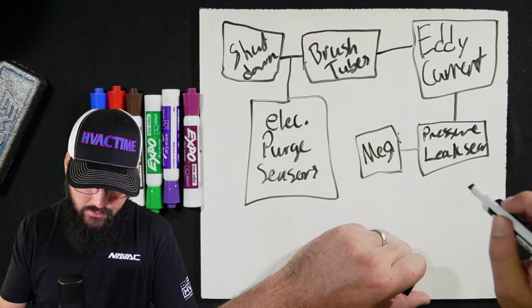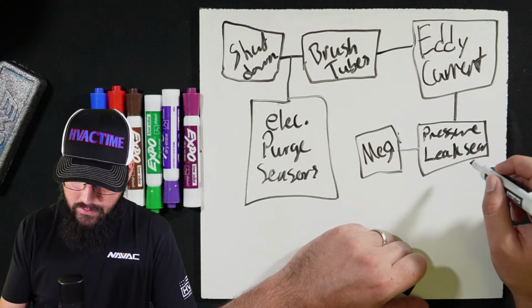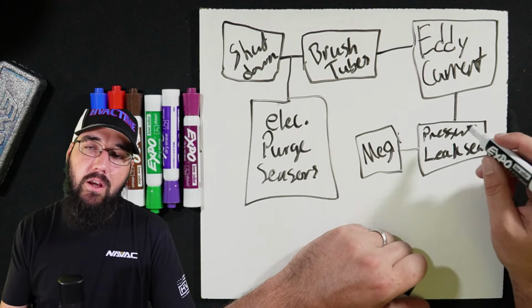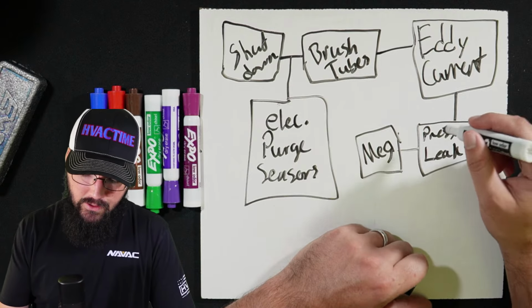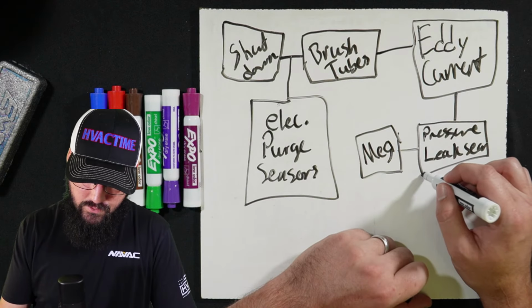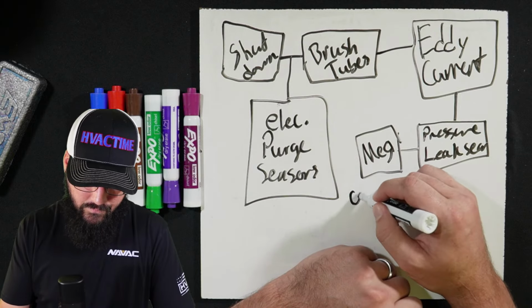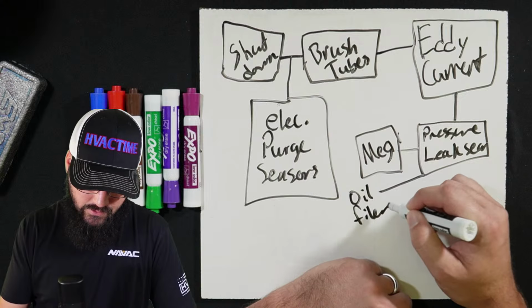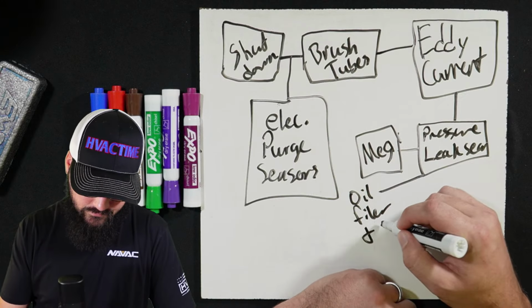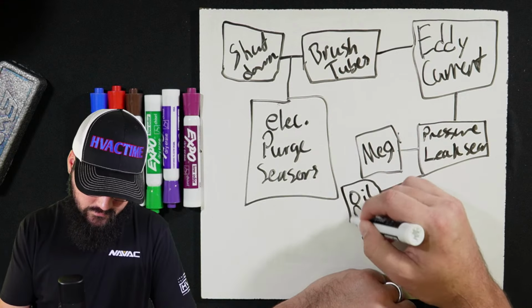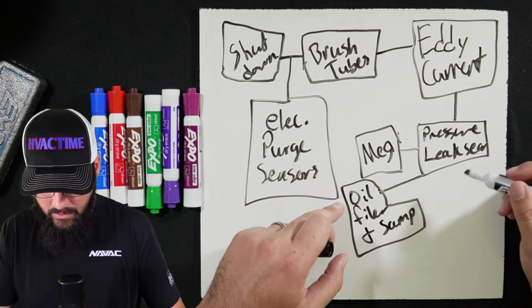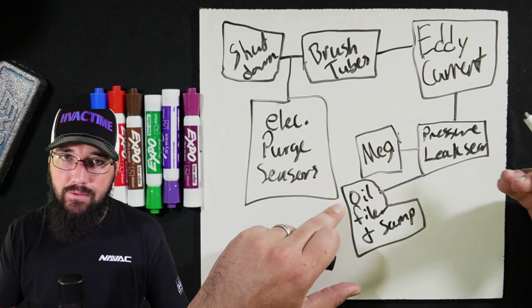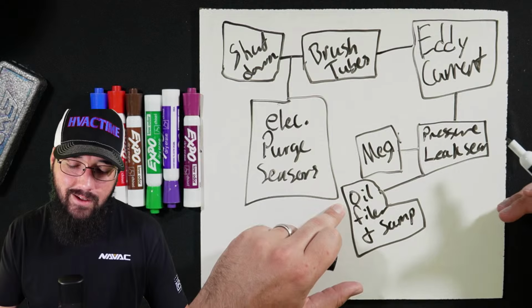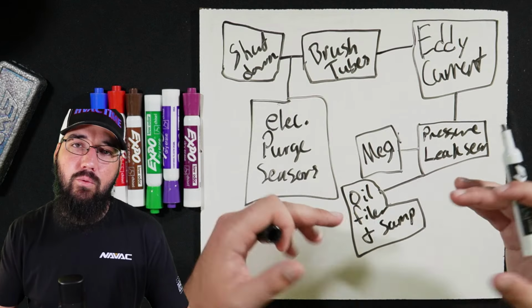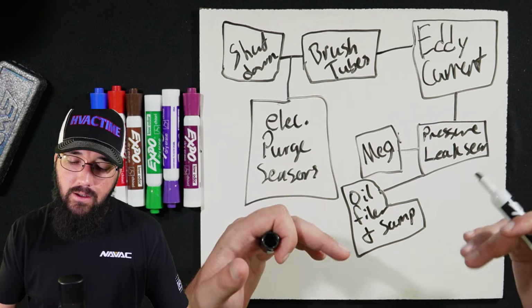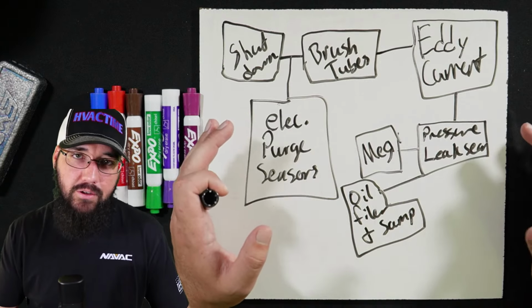This is also a good time to do the oil filter. So take another branch: oil filter and sample. Again, while we're pressurized, you don't have to do it while pressurized. This can technically get done later. It's just a really good time to do it so that you limit the non-condensables that get drawn in. Again, depending on if you're pressurizing at all.